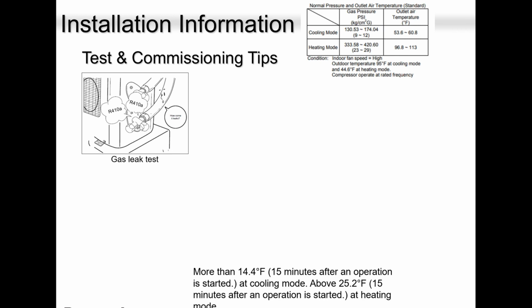Too much pressure will hurt the valve here. Look at my cursor. The valve over here and over here will get pushed in with too much nitrogen testing. And that can cause some of your 410 to come out, to escape. And when you're getting rid of the nitrogen, you will run away with some of the 410. And if you don't run away with 410, you might have contamination. So if you're doing this system during summertime, you may not see a problem, because in summertime, this compressor doesn't ramp up too much as compared to winter season. You will see the results in winter time. It starts to freeze, low on refrigerant, and you name it.